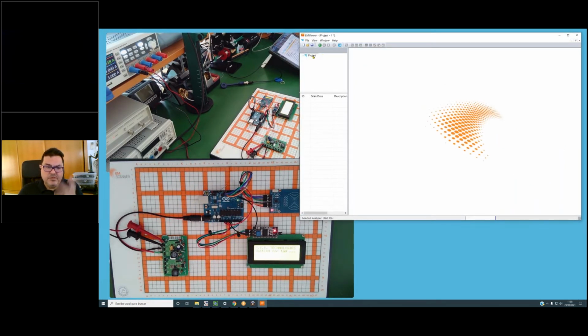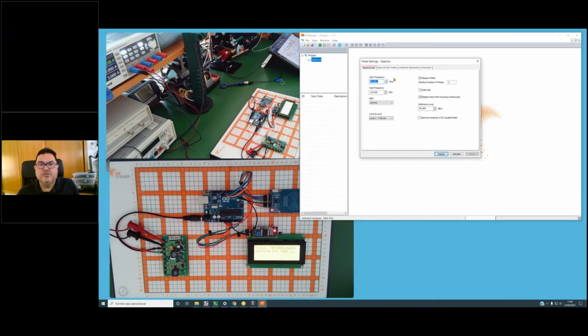Okay, what you do inside of the scanner is to create nodes. We have different nodes: spectral scans, spatial scans, spectral and spatial scan at the same time. We can combine with handheld probes. We can compare spatial or spectral scans very easily. Now, let me try to do a spectral scan. For the spectral scan, you need to specify what frequency range you want. Not too much. Try to put here the necessary frequency range. For example, from 10 megahertz up to 300 megahertz. Why? Because I have a problem at around 100 megahertz.